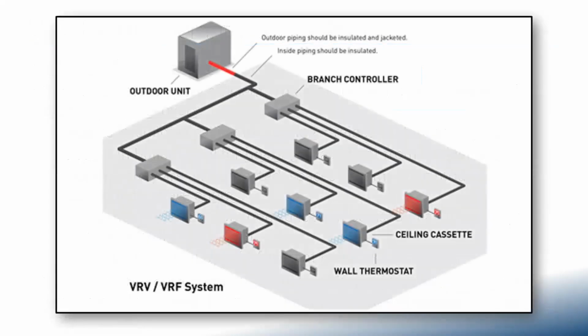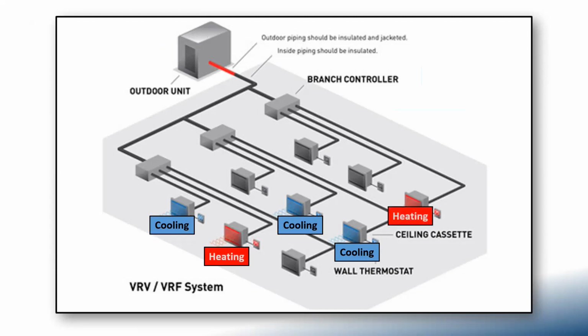Here's a basic schematic of what this might look like. So we have our outdoor heat pump. We have our 3 branch controllers. They kind of show it almost like it looks like one pipe, but imagine 3 pipes in each of these runs, and then 2 pipes out to each fan coil. And out in our system, we have, say, these 3 units. They're in cooling mode. And so those are pulling heat out of their spaces, putting it into the refrigerant. And then we have a couple units that are in heating mode. And now those units can use that heat. And then we got a number of units that they're happy where they're at.